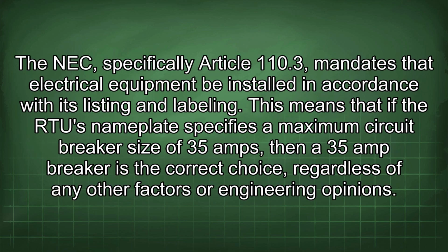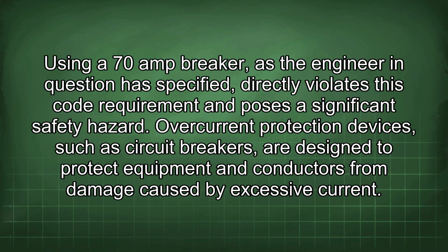The NEC, specifically Article 110.3, mandates that electrical equipment be installed in accordance with its listing and labeling. This means that if the RTU nameplate specifies a maximum circuit breaker size of 35 amps, then a 35 amp breaker is the correct choice, regardless of any other factors or engineering opinions.